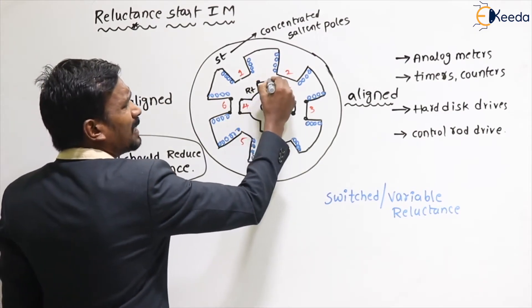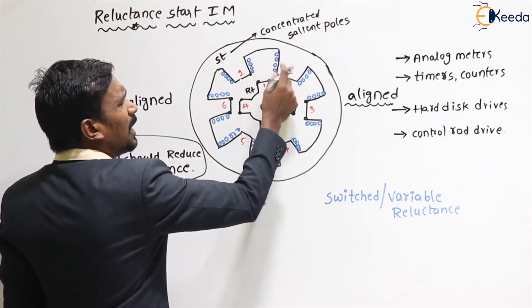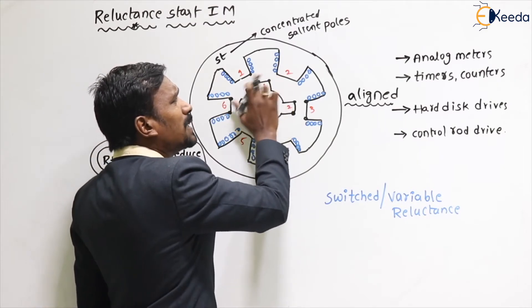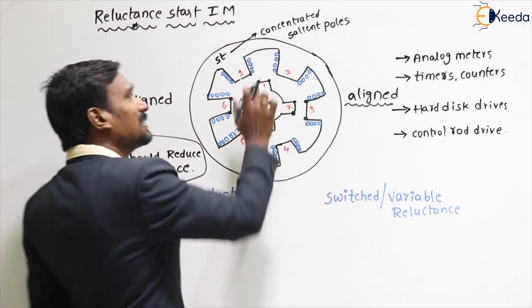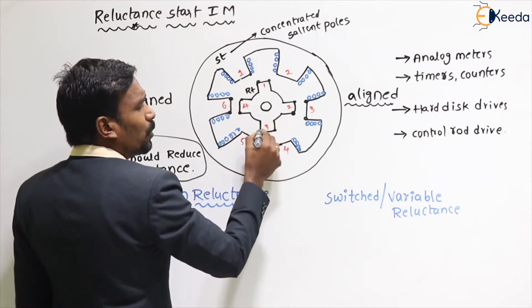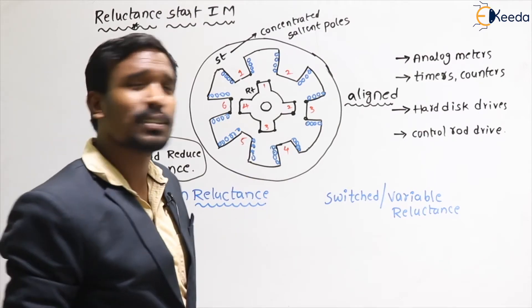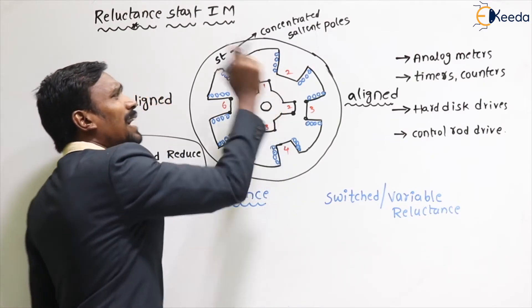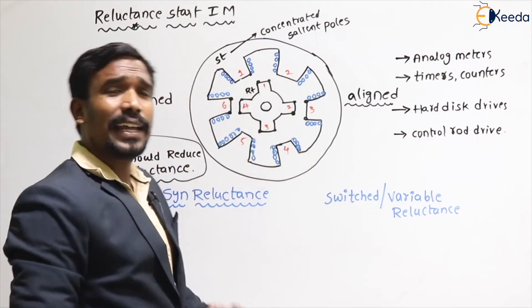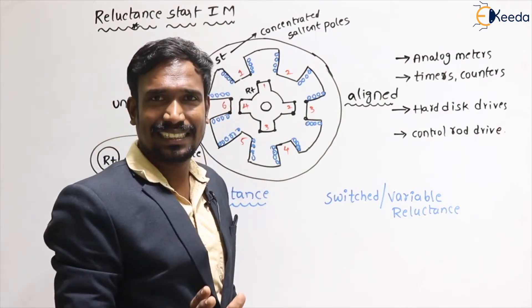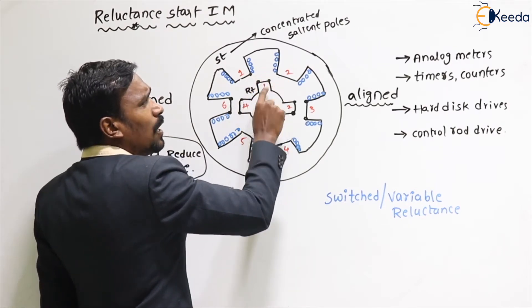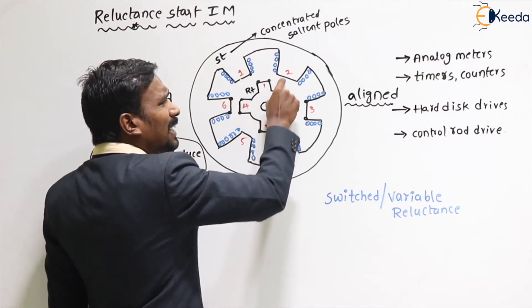When my rotor is exactly in between two poles of the stator — exactly in the middle — the reluctance is maximum because the air gap is maximum. Then my rotor tries to reduce that reluctance, so the rotor rotates.